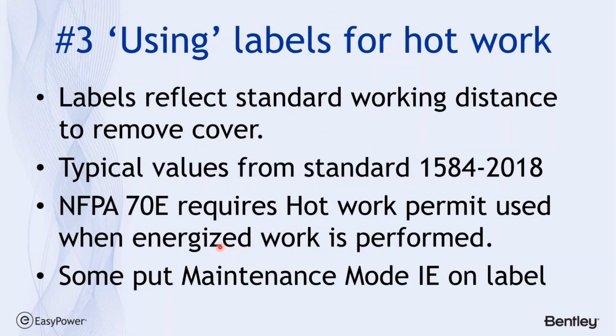Now here's the soapbox that I stumble over virtually every time the topic comes up. And that is the intent or the activity of using labels for hot work. A label reflects the standard working distance to remove the cover. In other words, if the cover's on the bus work, the cover's on the panel, and it's been installed and maintained per manufacturer's instructions, there's a relatively low probability of an arcing fault or an arc hazard if I'm not engaged in moving any element on that bus. Now, the typical values from the 2018 version, as I mentioned, for working distance are given in the standard itself.